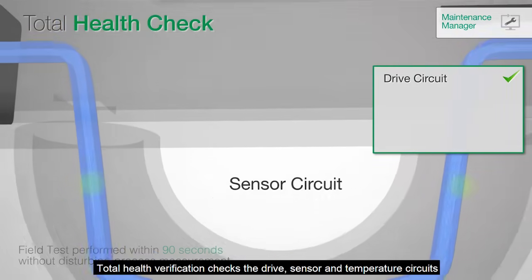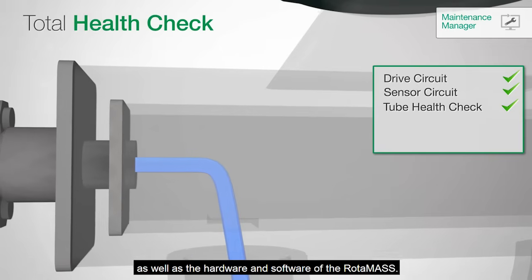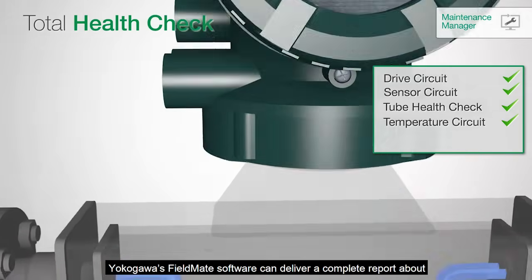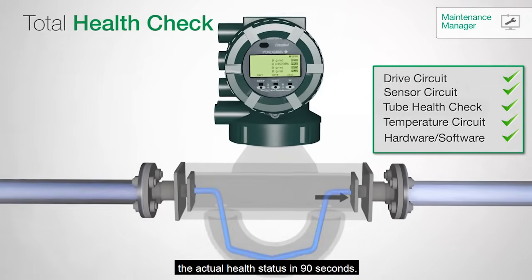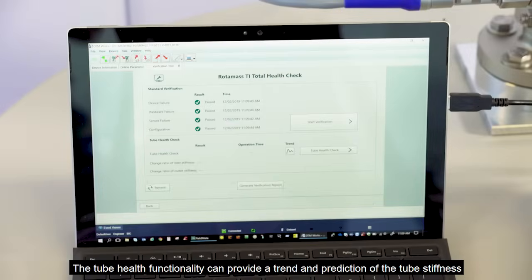Total health verification checks the drive, sensor, and temperature circuits as well as the hardware and software of the Rotamass. Yokogawa's Fieldmate software can deliver a complete report about the actual health status in 90 seconds.